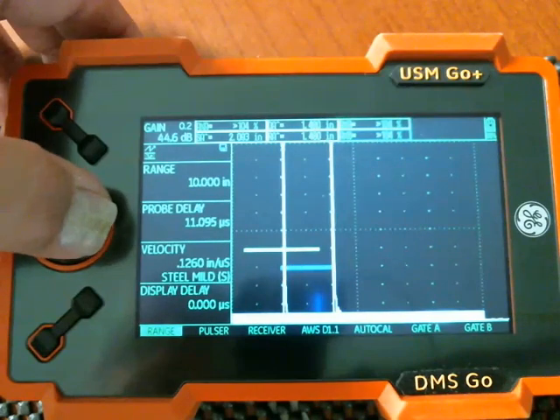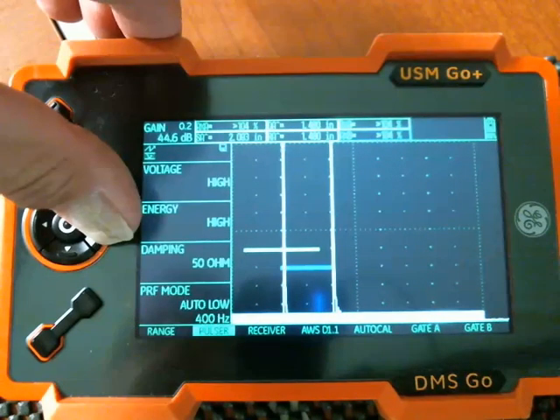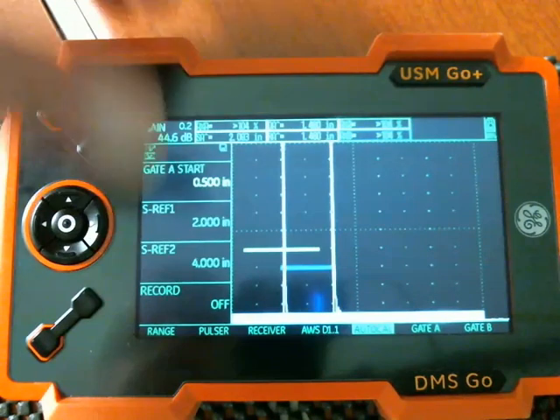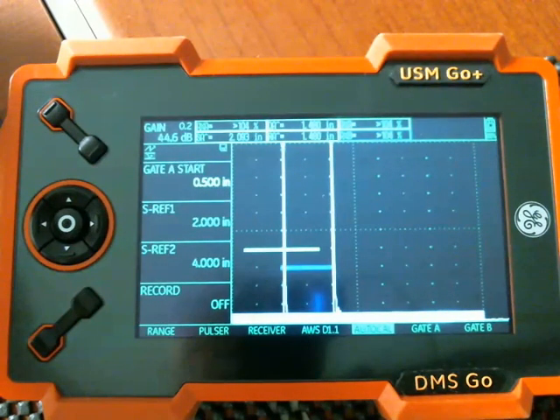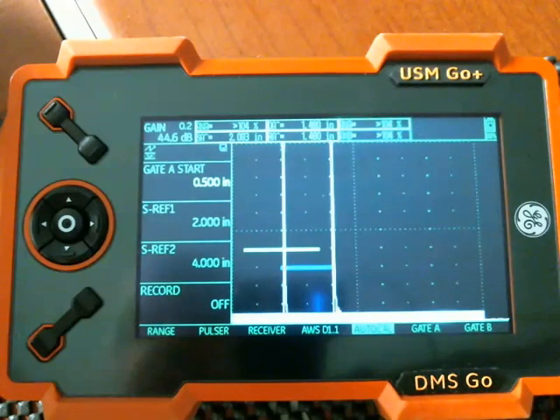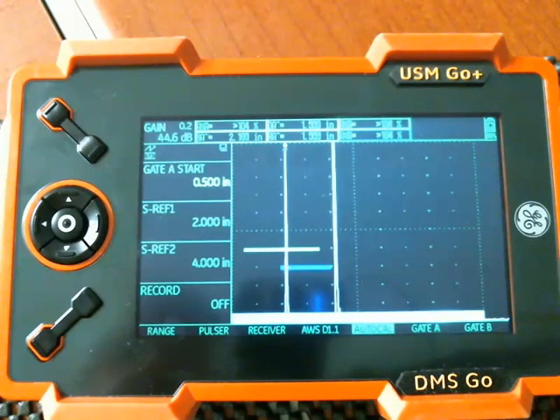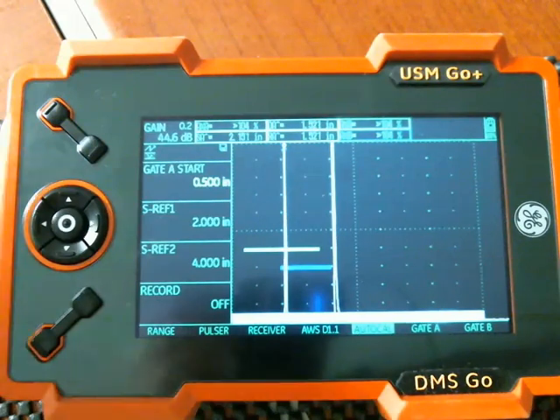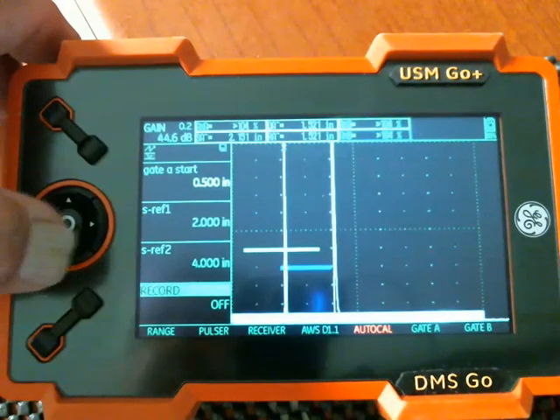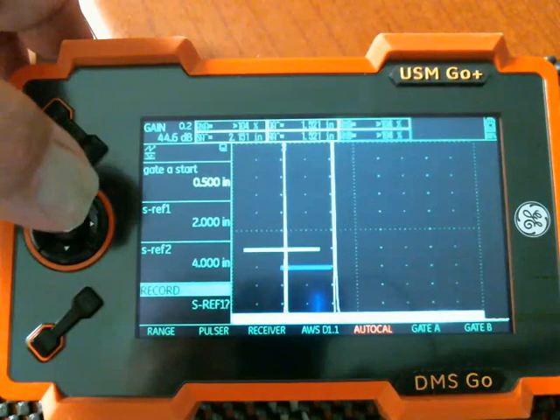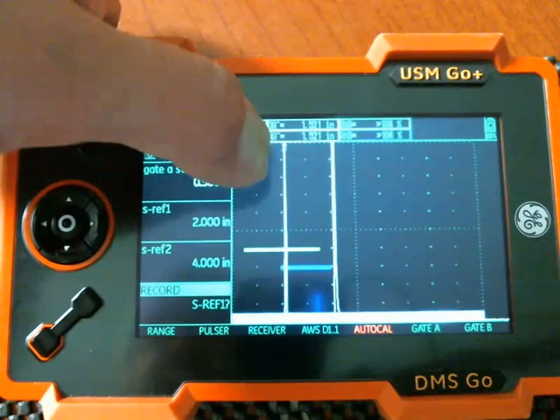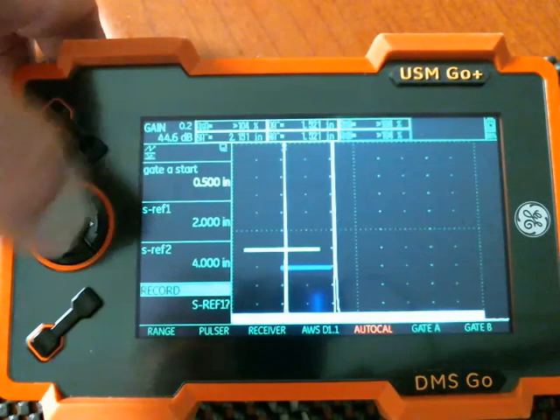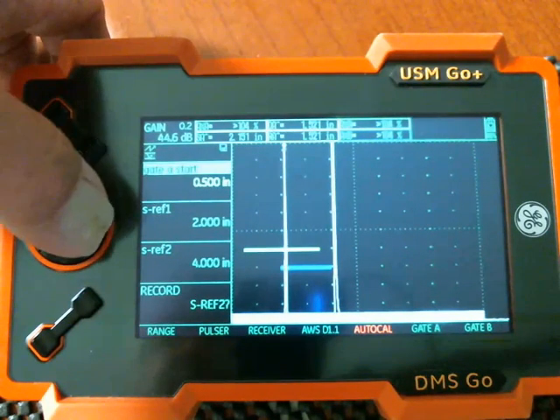So now we go back out to the main menu. And first we're going to do an auto calibration. And what this does is it's just a basic two point sort of distance calibration. We're going to calibrate on the two radii of my IIW type 2 block. And again, they're at two inches and four inches. So I'm going to come down here. I'm going to start the recording process. It says S-REF1, meaning put gate A over the first indication at two inches. It's already there. So we record that.